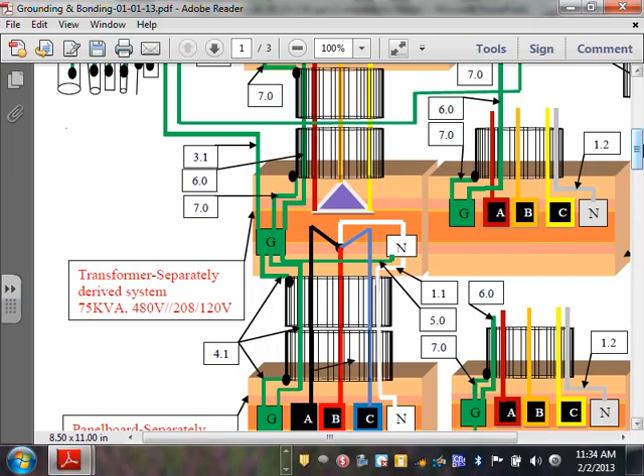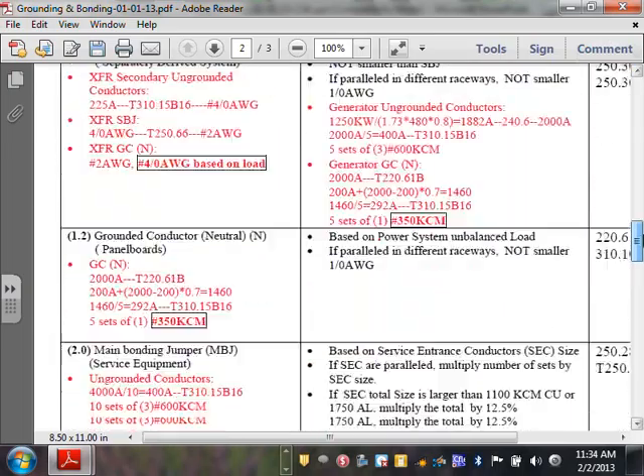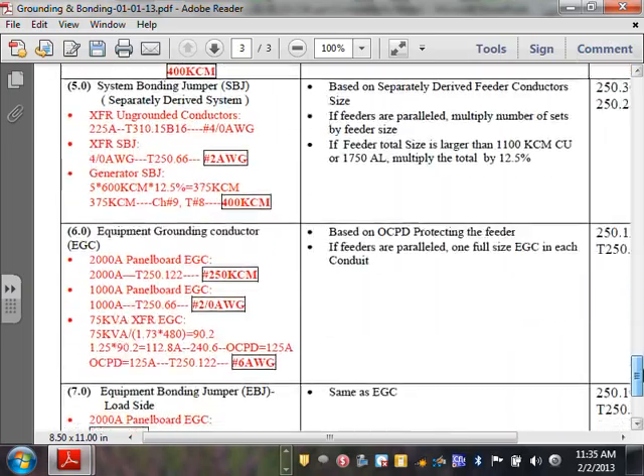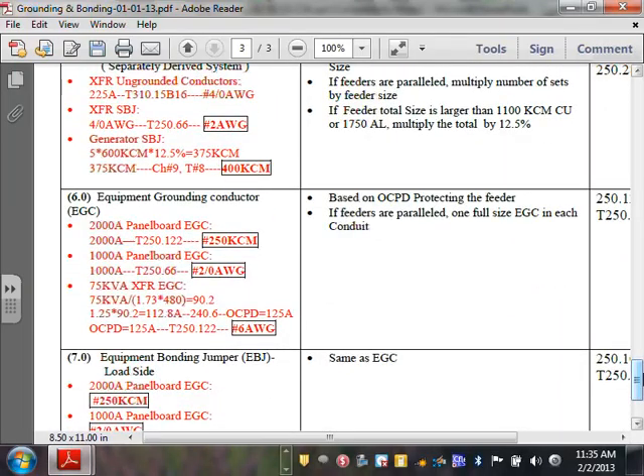No. Number 6 is an equipment grounding conductor. Number 3.1 is a grounding electrode conductor. Let's go to size number 6. If you guys go to number 6, good point. Number 6 for the transformer. Just go all the way to the transformer right here. Number 6 for the transformer, guys. Now, number 6 is the equipment grounding conductor for the transformer.